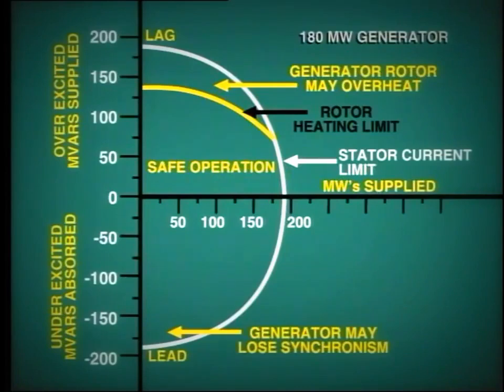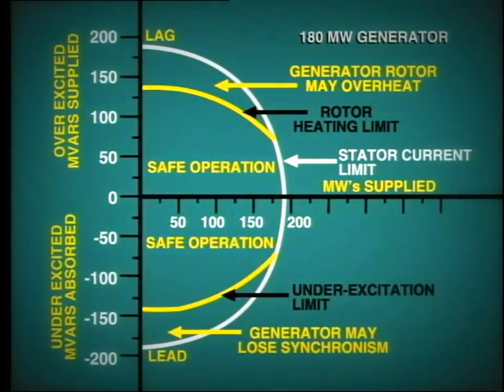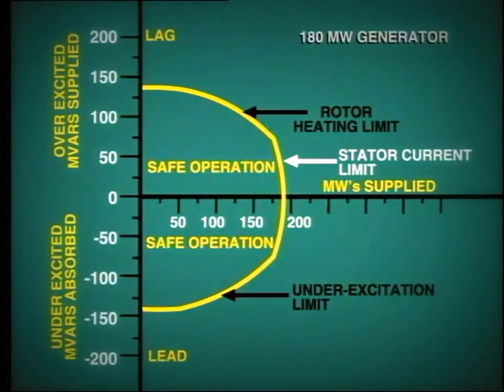In order to prevent this, a minimum excitation limit is established, which is given by this additional curve here. This combination of limits provides the generator capability curve that you should be familiar with.